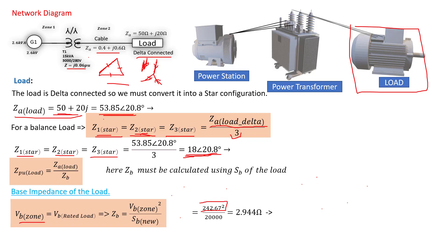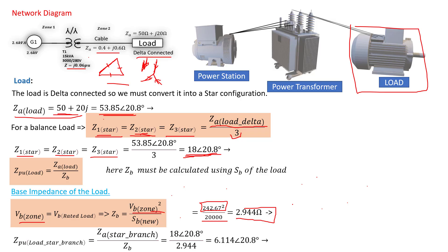We square V_B zone as per the formula, divided by S_B new — our S base — and we find a Z base value of 2.944 ohm. That is the base impedance of the load. We now have the Z actual for each branch of the star and the Z base of the load, so we can go ahead and calculate Z per unit of the load for each star-connected phase.